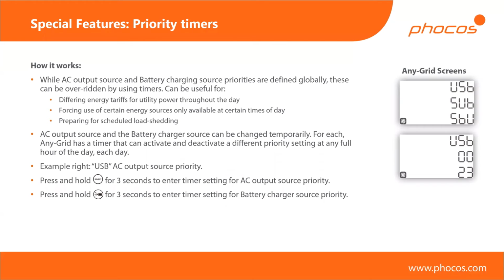Now we have the priority timers as another special feature for these devices. So I've explained the AC output source priority, so what you're powering your loads with. And then there was the battery charger source priority. Both of those are important to set up the basic functioning of the unit. But now you can go in and actually override those settings for a certain number of hours per day. So this, I think, is particularly valid as a scenario if you really want to, for example, force something during the night, or you know exactly that there's a huge load which normally you don't have, which will turn on at a certain time every day, so you just preemptively want to switch to the grid or whatever.